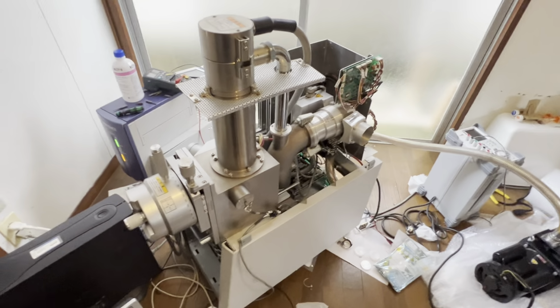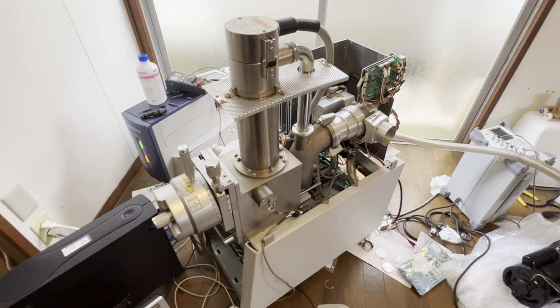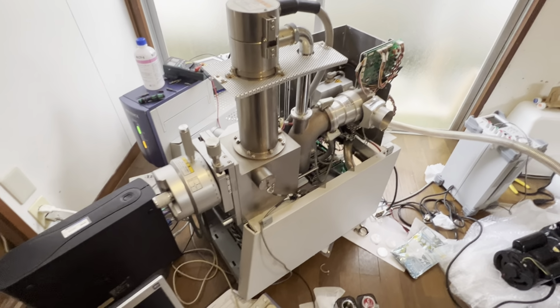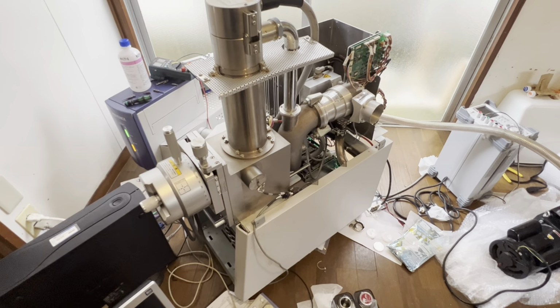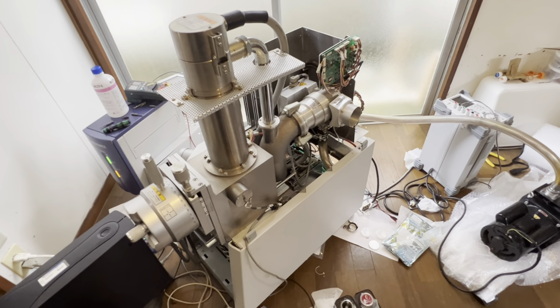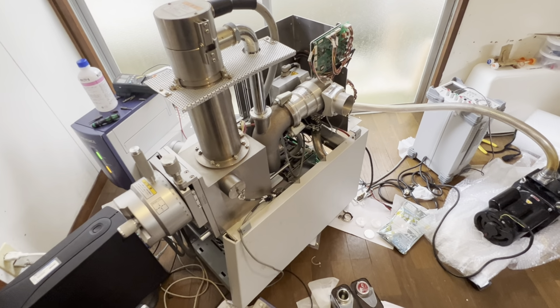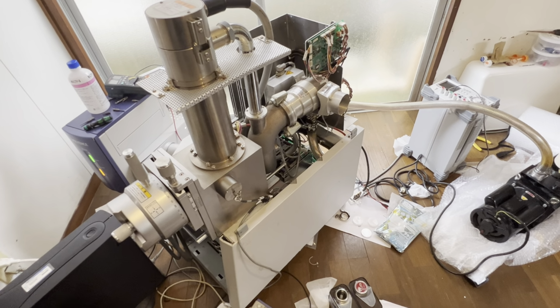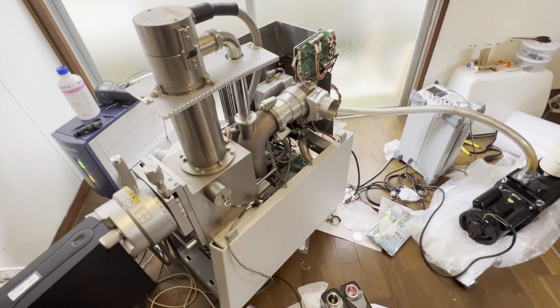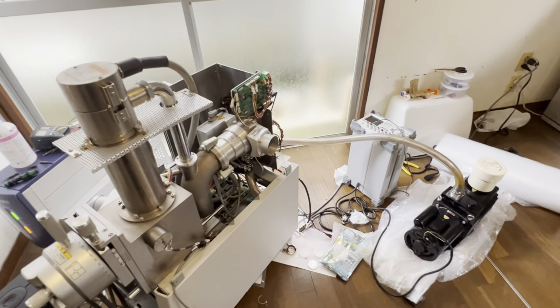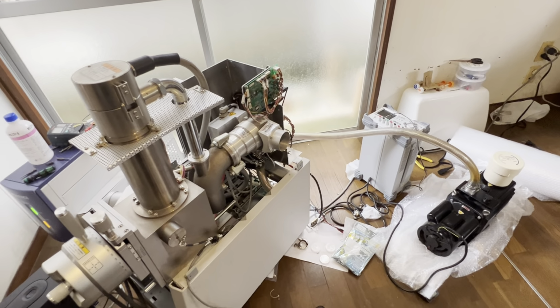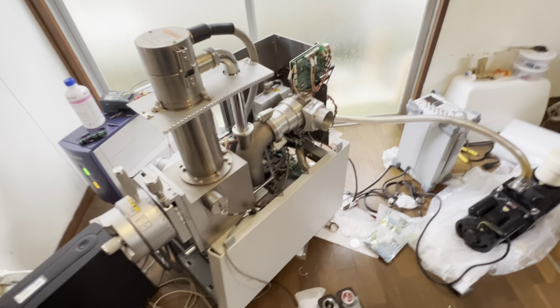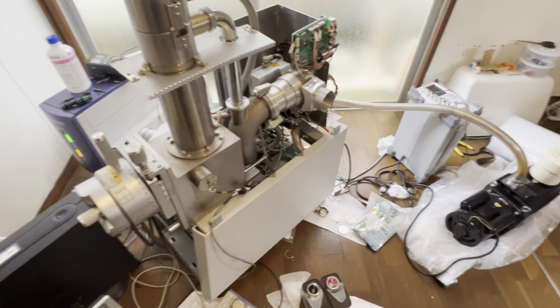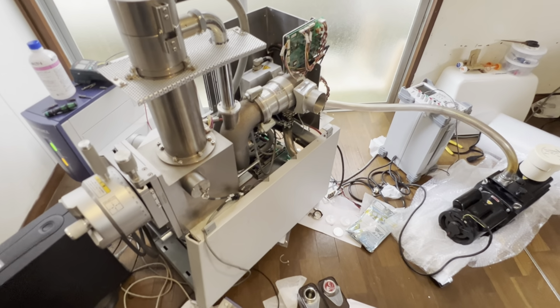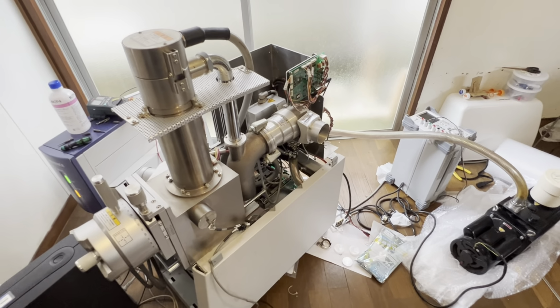When it comes on, it immediately turns on the roughing pump, and pretty much straight away sends a signal to the turbo to also come up. The roughing pump is just a regular AC connection - it doesn't seem to check that there's any kind of load on that. So if the roughing pump is not plugged in and someone just presses the button, or plugs it in, because as soon as you plug in the system it will try to come up, the turbo will just come up in atmosphere.